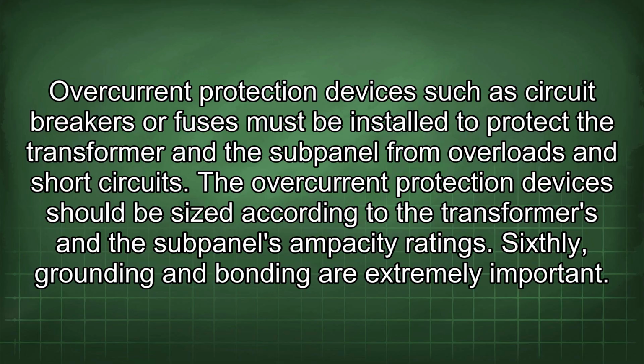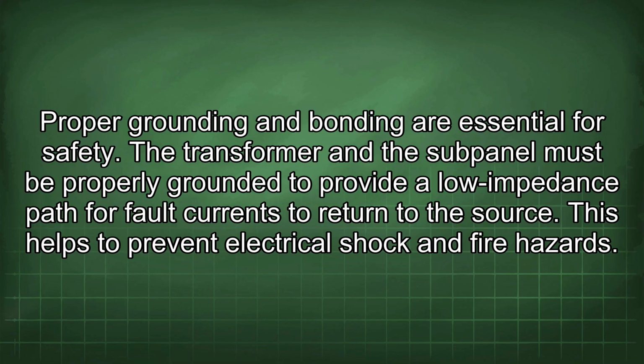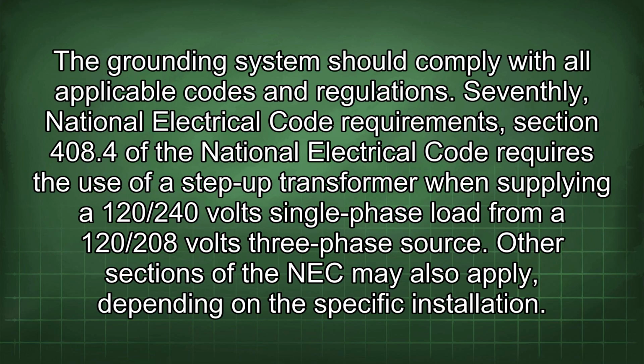Sixthly, grounding and bonding are extremely important. Proper grounding and bonding are essential for safety. The transformer and the subpanel must be properly grounded to provide a low impedance path for fault currents to return to the source. This helps to prevent electrical shock and fire hazards. The grounding system should comply with all applicable codes and regulations.